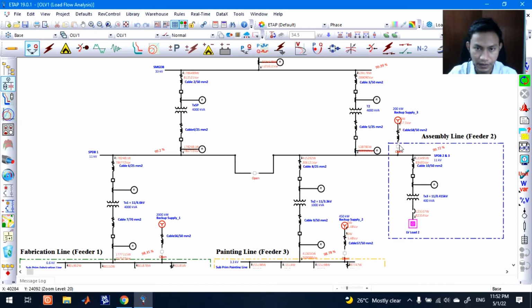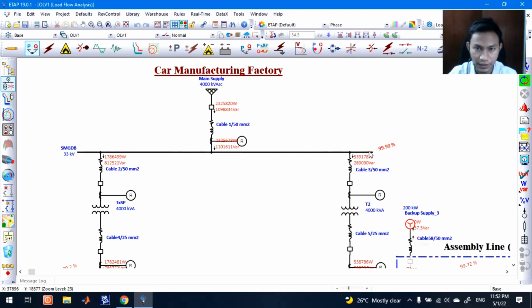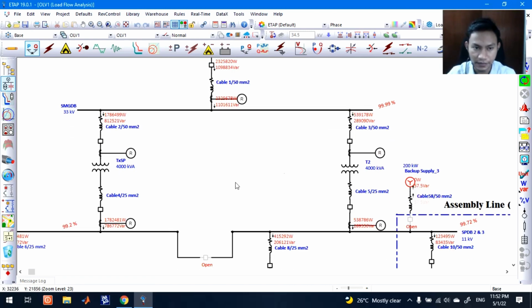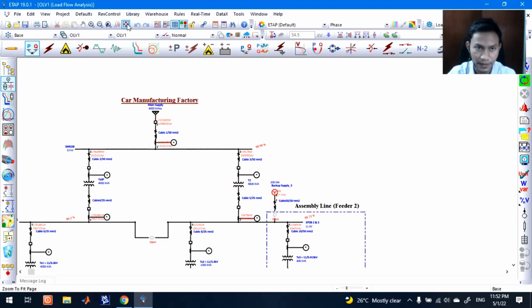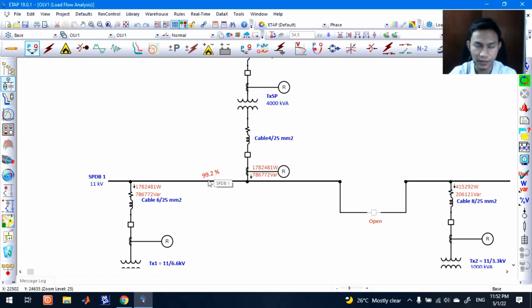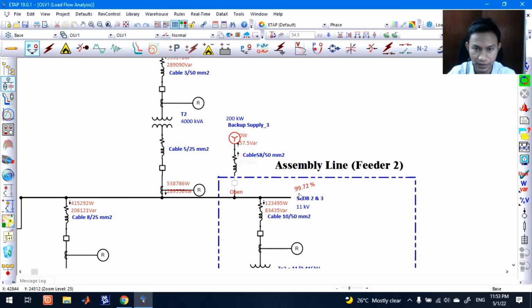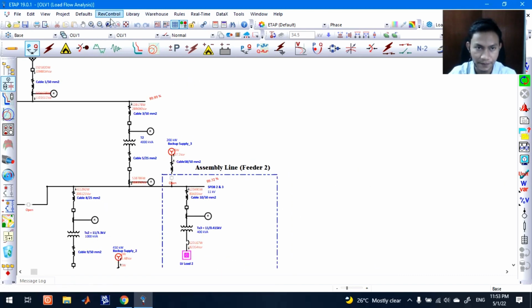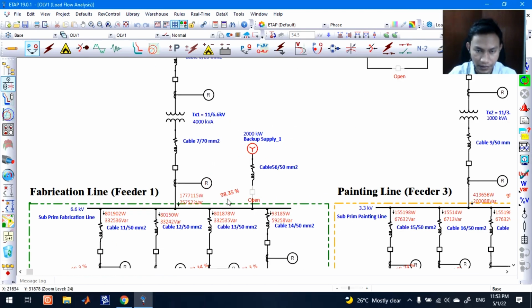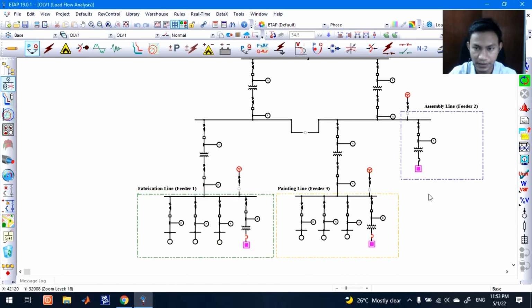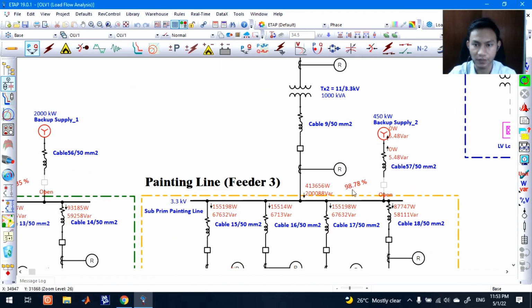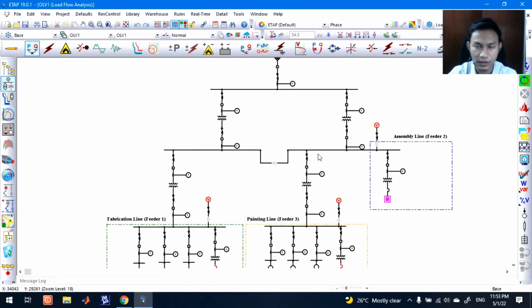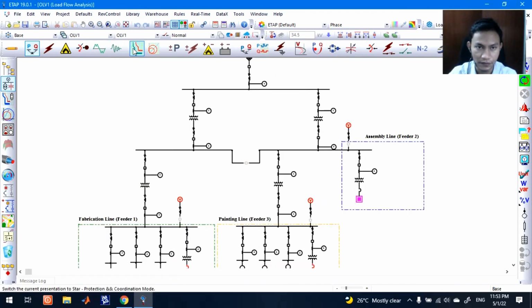Basically, the voltage from TNB is 99.99%, which is below 10% drop. At the SPDB it is also below 10% drop, which is 99.92%. From SPDB 2 and 3 it is 99.72%. At feeder 1 it is 98.35%, and for feeder 3 it is 98.78%. So basically all the voltage drops are below 10%. So we proceed to the fault analysis.